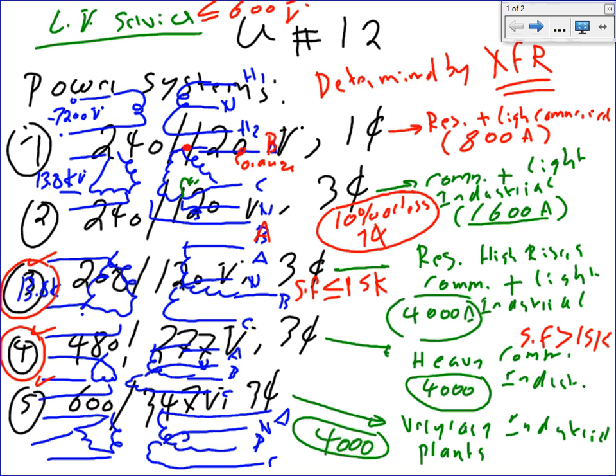Look at all these services: they are on the secondary side. On the secondary side, they're equal or less than 600 volts. The primary side, I care less. It could be any voltage. Most of the time, the primary is going to be 13.8, 7.2 if it's single phase. There's another voltage, guys, 4,160 volt, used in certain communities. But I'm caring about the secondary side, because that's where I have my control over my transformer, right in here. Okay, I bring to your attention low voltage service, less than 600 volt.